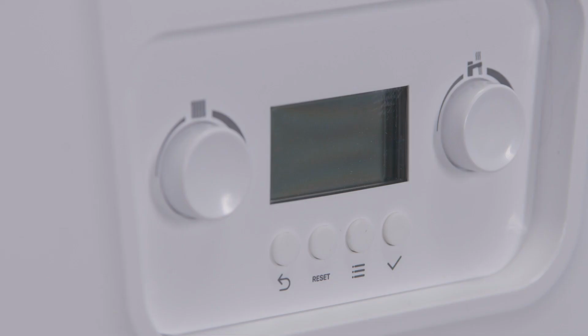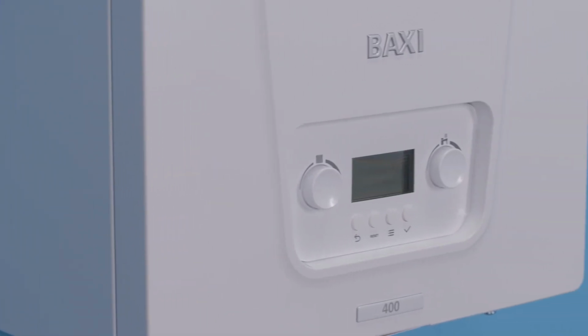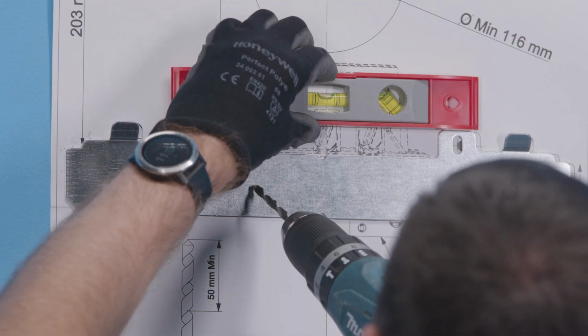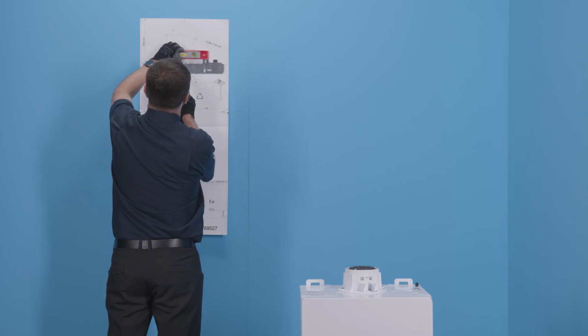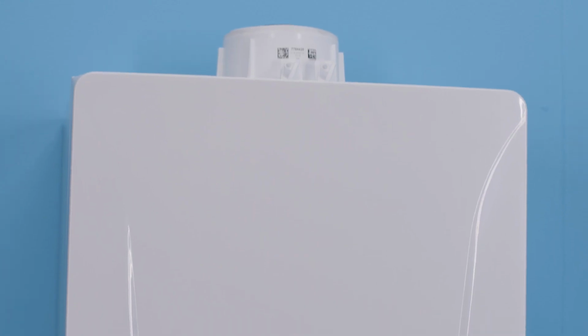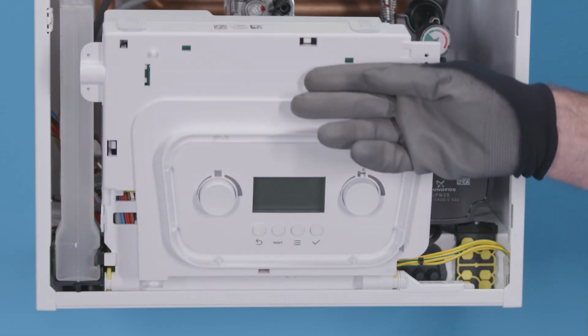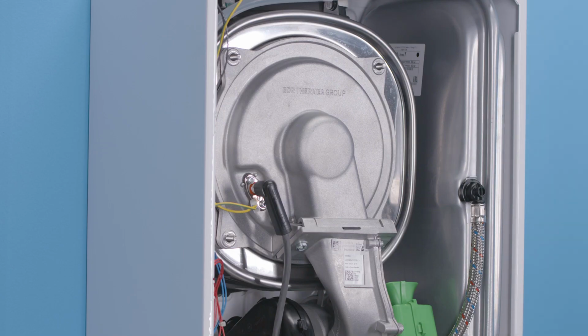Now I'll recap on the main features and benefits of the 400 Combi 2 boiler. It's a compact cupboard fit boiler that can be installed in a 300mm deep kitchen cupboard. Got a simple hanging bracket with a low lift weight of 30 kilograms, so it's easier and safer for installation. Top and central flue positions using our multi-fit options up to 20 meters. It's compact yet spacious. All components can be easily removed from the front, and it's got a stainless steel heat exchanger for proven reliability and peace of mind.